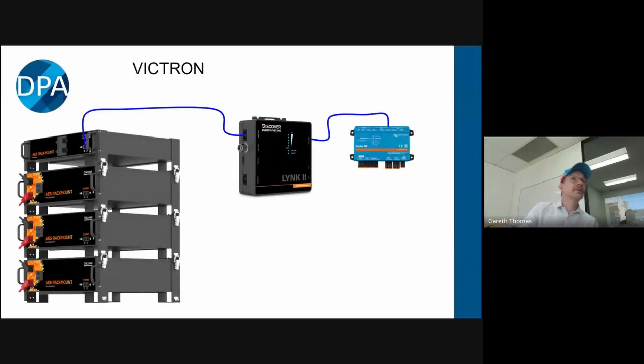So let's do an example system here. If we're doing Victron, you're going to take an RJ45 cable from the top battery into the Discover, and then from the Discover into one of the CAN bus ports on your Cerbo. You can see here we've actually got it coming out of the combiner box, because the combiner box has a set of RJ45 plugs, allowing you to daisy chain through the batteries as well. It also has an on-off switch on the combiner box, which will turn the rest of the stack off and on.